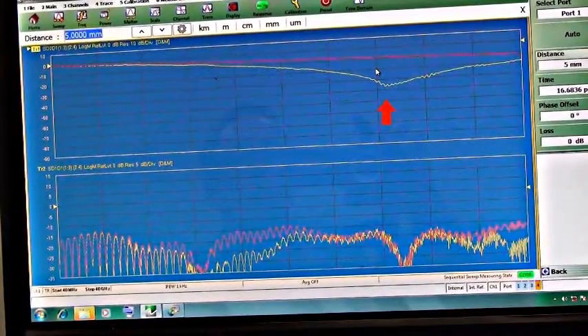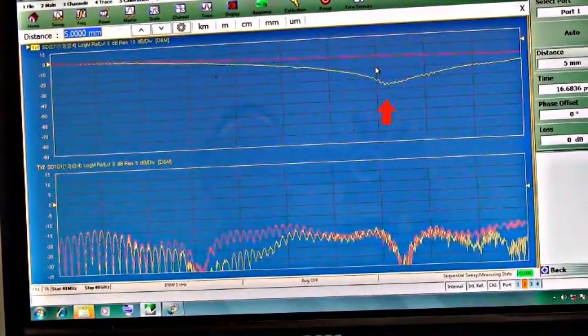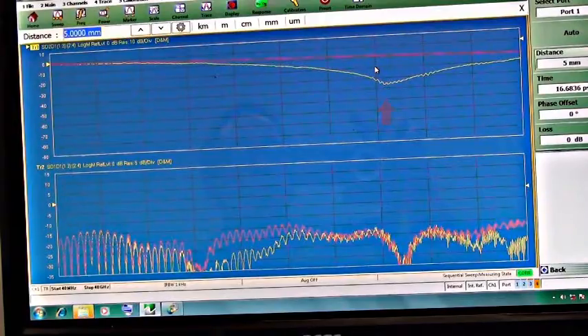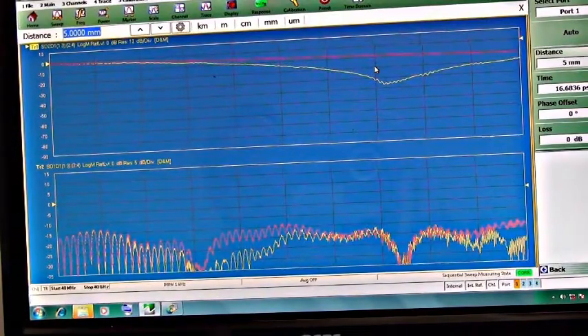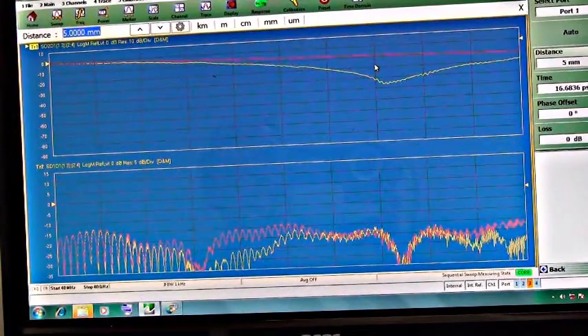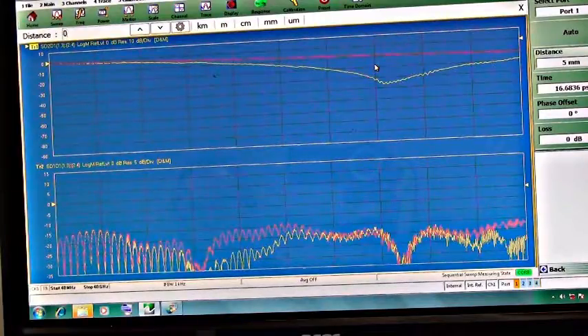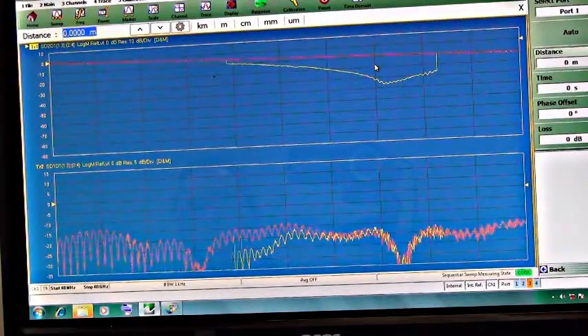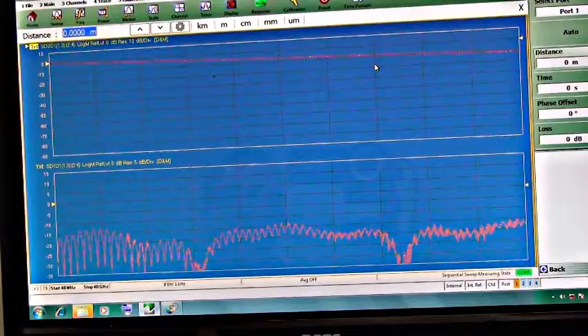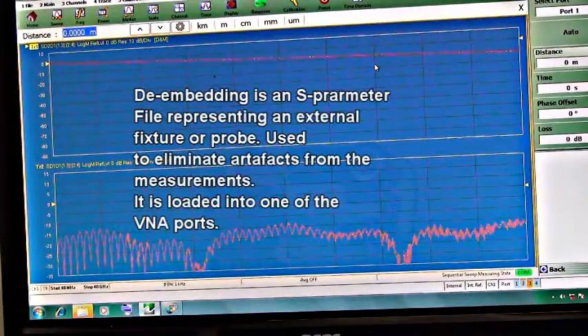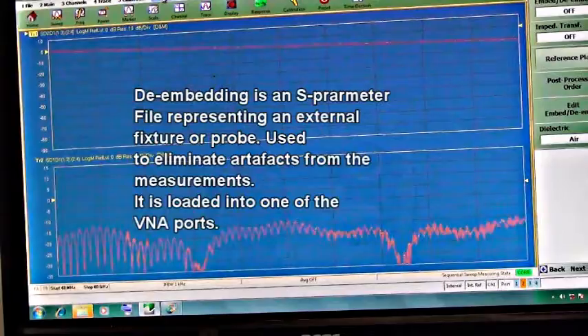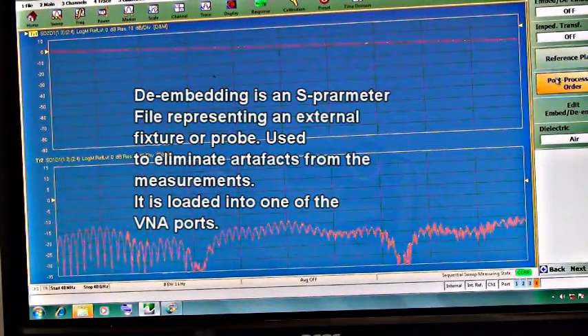So if I see a condition like this, then I know I could have something wrong with my setup, or I just could have a bad calibration and I need to go back and recal. Another thing that's quite often found in setups is the de-embedding. Whenever you're working with a structure, or somebody has de-embedded a fixture or a line, sometimes they forget to turn that back off before they do a calibration. If you run into a situation like that, it's going to look similar to this one.